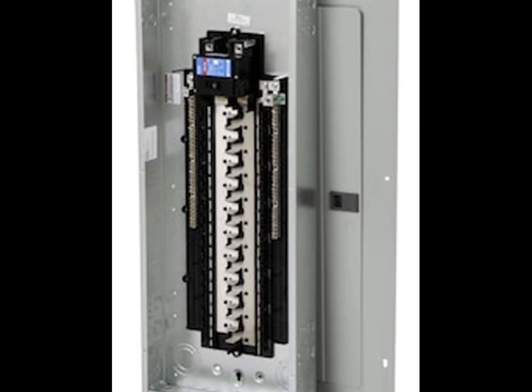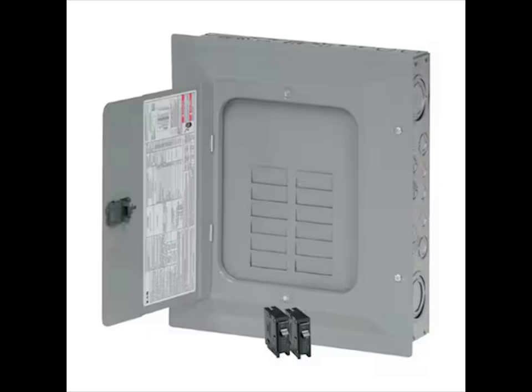My load center had only 40 slots for breakers. This was not enough. I added a secondary circuit breaker box with 12 more slots. It is a BR 125 amp, 24 circuit, 12 space main lug indoor plug-on neutral load center, model number BRP12L125V24. This panel is rated to 125 amps. I elected to use a 100 amp breaker in the main panel.